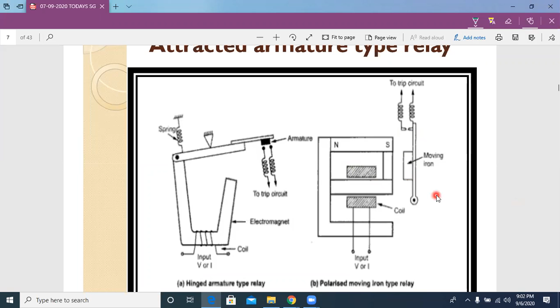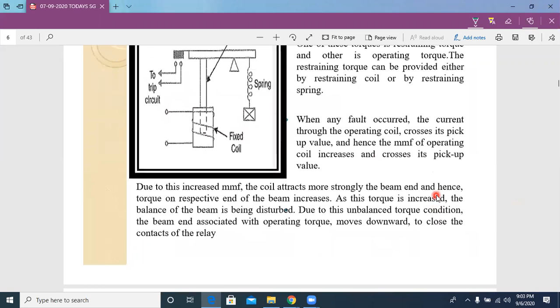When the magnetic coil is excited, that means when the current reaches more than the preset value, this particular element acts like an electromagnet. When current flows in this coil, it acts like an electromagnet. This electromagnet attracts the moving iron when a fault happens in the system. When it attracts the moving iron, these contacts are closed. When these two contacts are closed, we can see current in the trip circuit. In this way we can explain electromagnetic armature relays.